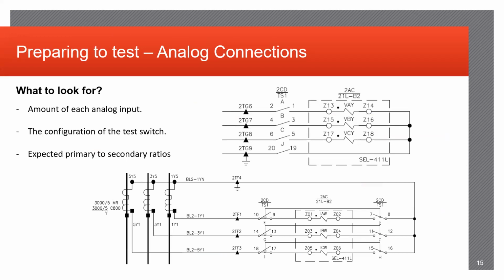All right, going back to a point I made earlier, verifying your analog connections from your test set directly to the relay. So as shown here, we can identify that this 21L B2 is the relay we're going to be testing. As shown in the 3-line schematics, your voltage and current sources coming into the relay is correctly identified. There would be more of a section for this voltage class going back to the PTs to verify ratios and phasing as well, as shown as the current here.